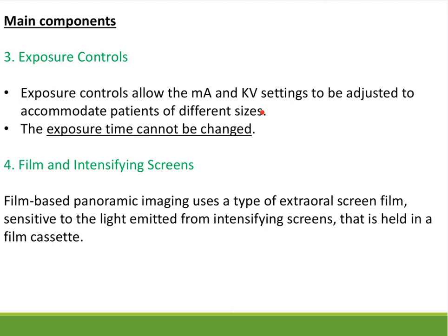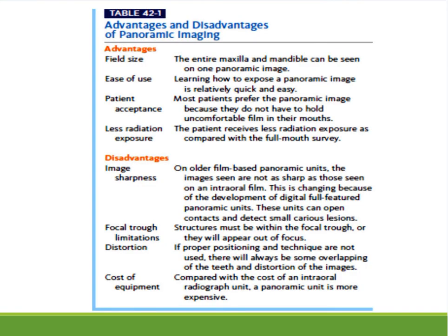Film-based panoramic imaging uses extra-oral screen film sensitive to the light emitted from the intensifying screen. If the intensifying screen emits green light, the film must have a dye sensitive to green. Other options include blue light and ultraviolet radiation. This is called a screen-to-film combination. The color of light emitted by the intensifying screen must match the sensitivity of the film — if the screen emits green light but the film is sensitive to blue light, it will not produce a good image and will result in radiographic noise, fogging, or lack of clarity.